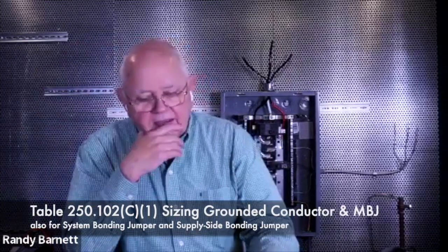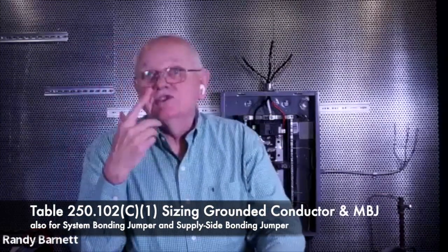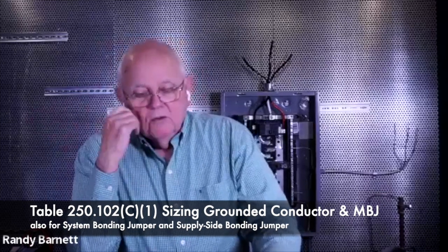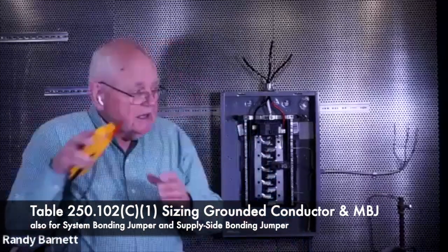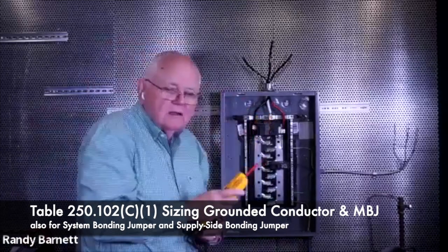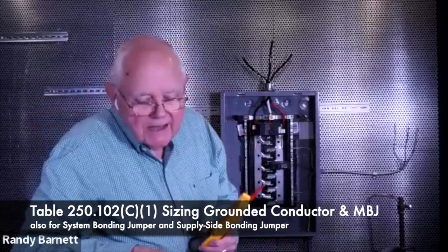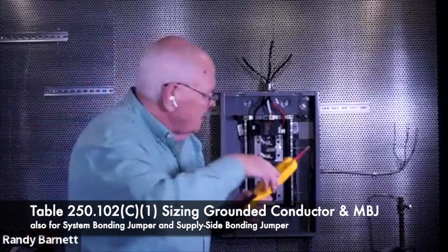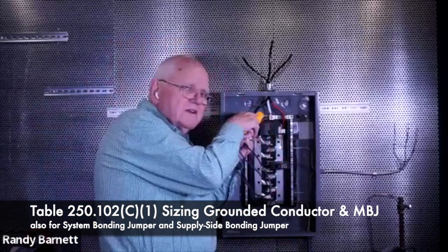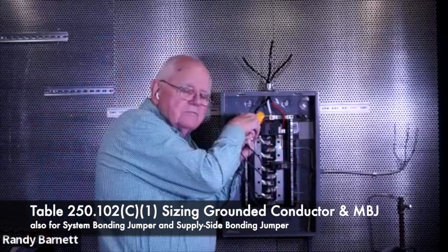Now, there's another table that we're going to use for sizing. Well, let's go take a look at it because it's several different things. It's table 250.102(C)(1). We use it to size the grounded conductor up here. We use it to size the main bonding jumper. Main bonding jumper, that's that green screw right there. We'll talk about it a little bit.